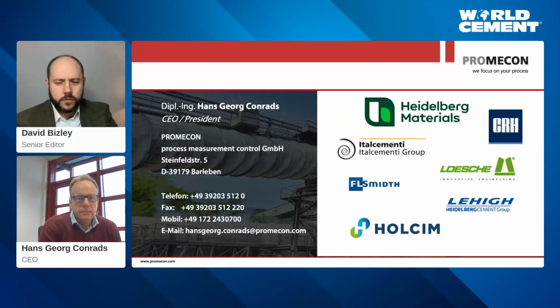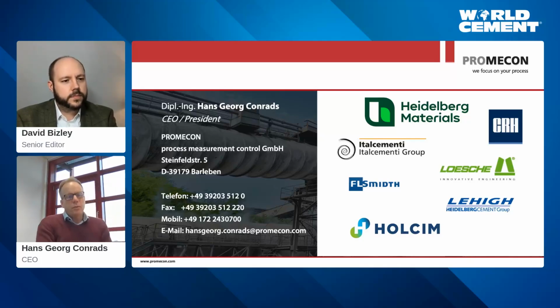Okay. And related to that, does installation have to take place whilst the plant is down then? Most people do that. We also have clients that say, oh, we can do this while the plant is running. We have negative pressure in our pipe. Then with special care and special protection, we can weld the bracket on, and after that we drill a hole through that. Yes, but the usual procedure is that people wait for a short outage, doesn't take long, and then they put it on.